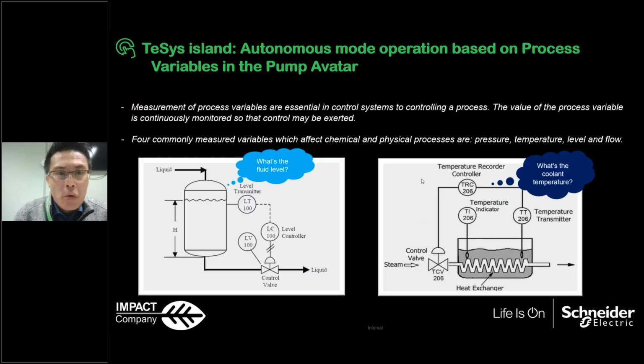Okay, so I think we talked about this before, the autonomous control based on the process variable. So let us talk more details on that. This is very interesting for the autonomous control, that you no need to have a PLC for such a control for the pump applications, and you can achieve it all with the TeSys island only. So let's say we measure the process variables, for the level sensors or the control system. The values for this process variable are continuously monitored. So that's when we can control the system, the motor on and off, based on these variables.